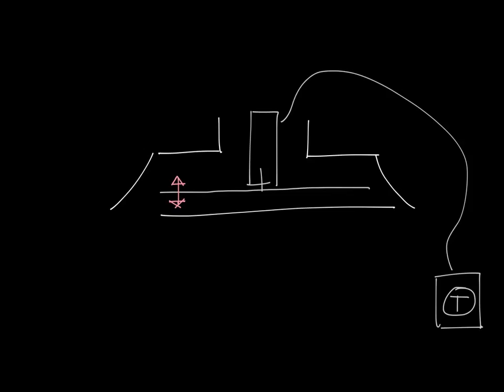So let's say this diffuser is in cooling mode and the space temperature is 72 degrees. And the set point is 75 degrees. So the damper will move up and down to control the temperature. In this case, it'll close off a little bit to get the 72 degree temperature to a 75 degree set point.